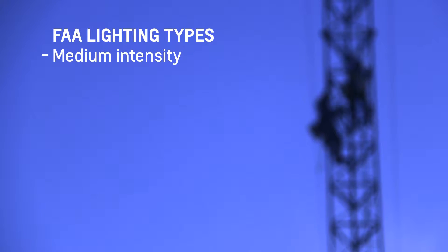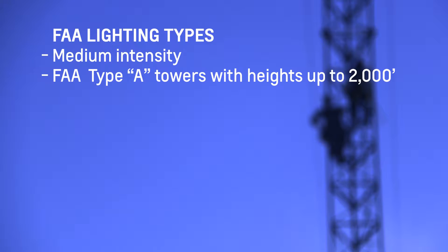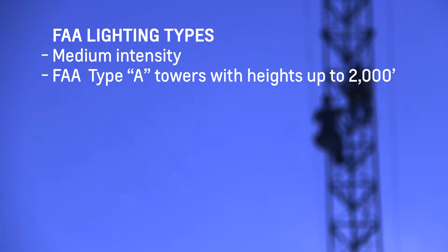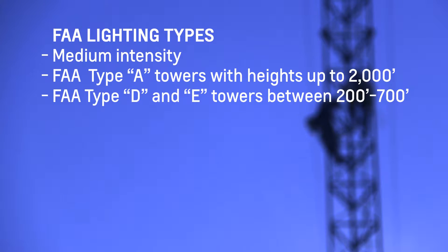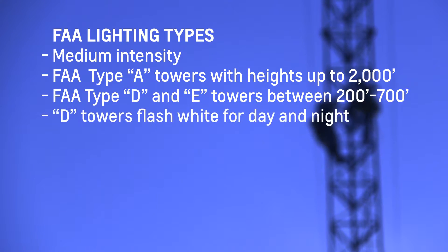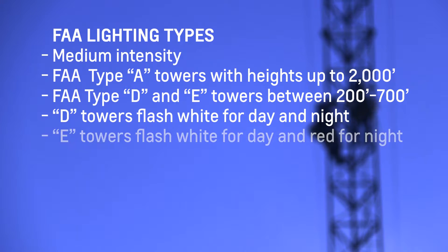FAA lighting types - Medium intensity. This lighting is used on FAA type A towers, which flash red at night and are painted with orange and white stripes. These towers can reach heights up to two thousand feet. Medium intensity lighting is also used on FAA type D and E towers, which are between 200 feet and 700 feet. FAA type D tower lighting flashes white for day and night, while type E tower lighting flashes white for day and red at night.